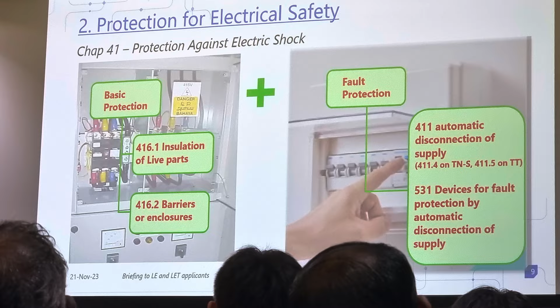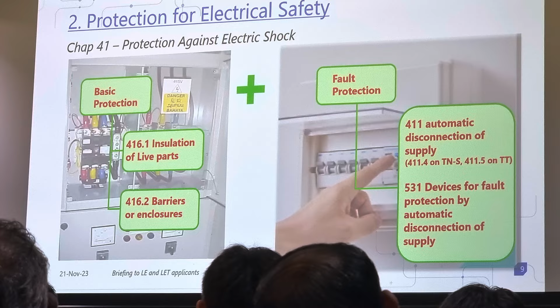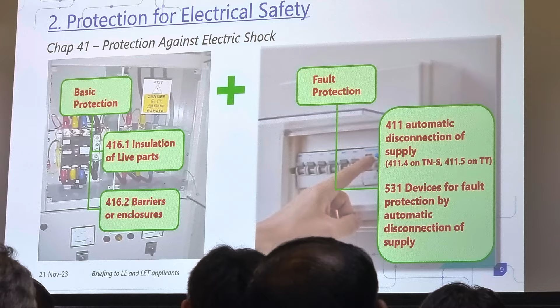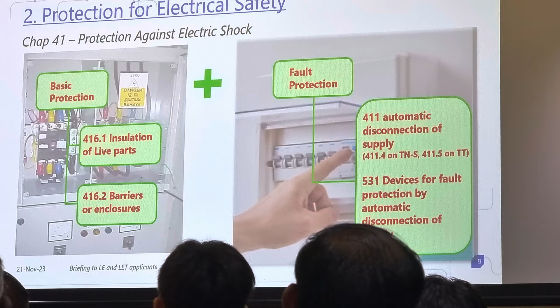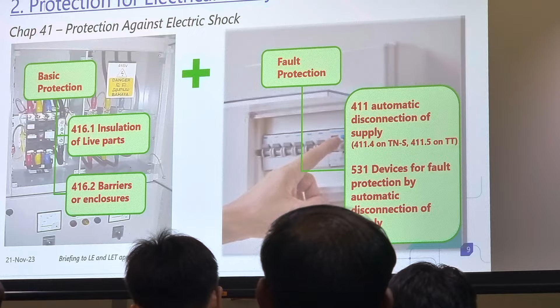We will also talk about the maximum duration. What's the maximum duration of time? There's the final circuit, the distribution circuit. There's also a time limit specified in the code. We tell you the maximum time which is allowed so the person can be safe. Right? So we talk about the touch voltage. Some of you know what we mean. So how do we use the touch voltage to work it out? To do that, we set protective devices to make sure the device will operate within the required time.